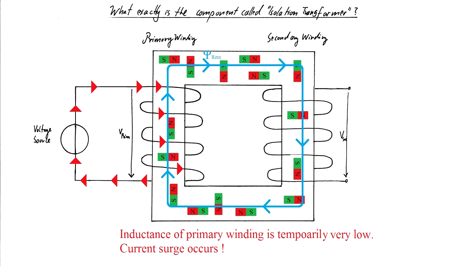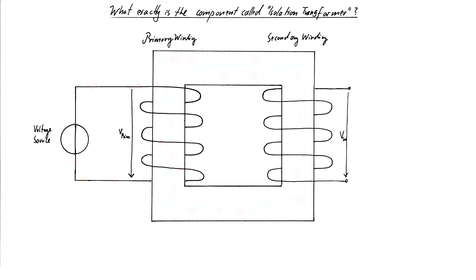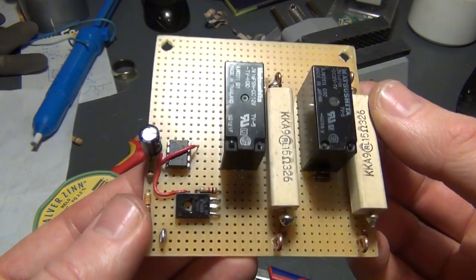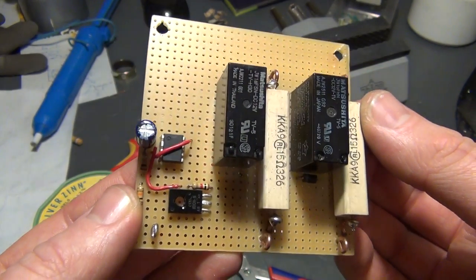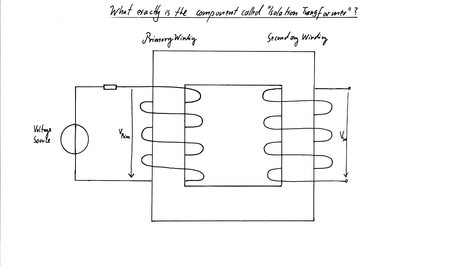In most cases in power electronics, magnetic saturation is a very bad thing, and we try to avoid it. To avoid the current surge, a resistor is connected in series with the primary winding, just like the one you see here. In parallel to the resistor, a relay is placed, which is supposed to close shortly after the current surge has been limited to acceptable levels.